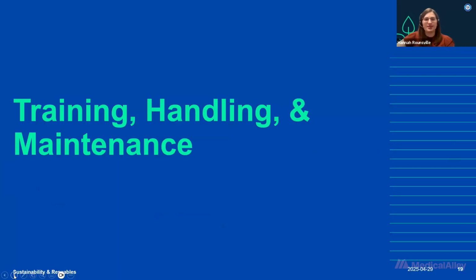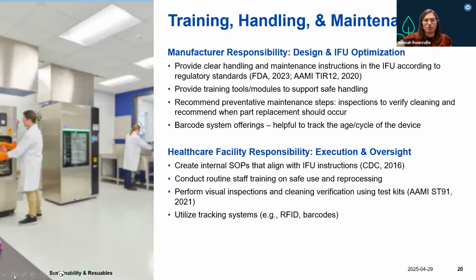All right, and as we wrap up the device lifecycle considerations, it's important to highlight the shared responsibilities between manufacturers and healthcare facilities in ensuring that reusable devices are handled, maintained, and tracked effectively. First, manufacturers must ensure that handling and maintenance guidance is clearly communicated in the IFU, aligning with current regulatory expectations. This should also include training resources to help promote staff safety when handling and reprocessing the device, particularly for complex or delicate instruments. Preventative maintenance should be emphasized, such as including recommendations for routine inspections, guidance on cleaning verification, and criteria for part replacement. Additionally, manufacturers can support sustainability and traceability by offering barcoding systems or tracking solutions, which allow facilities to monitor the age, usage cycles, and maintenance history of each device, as Jessica mentioned.